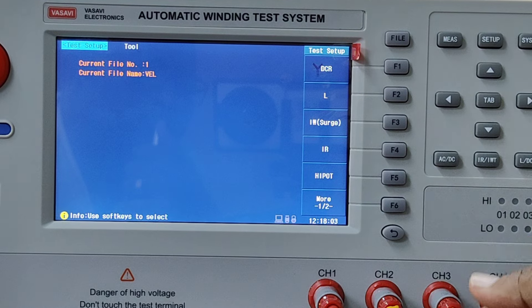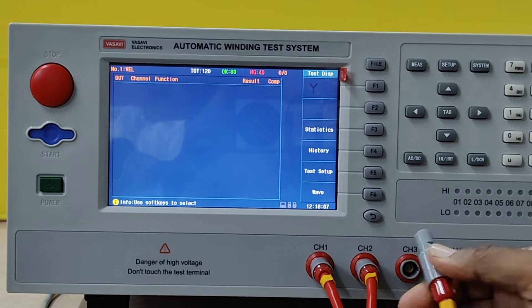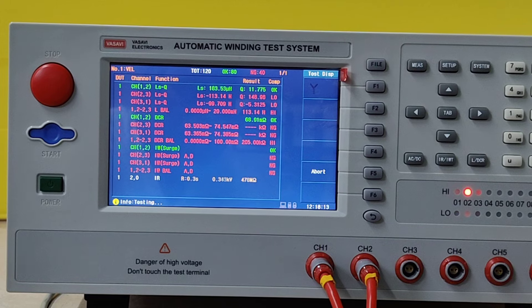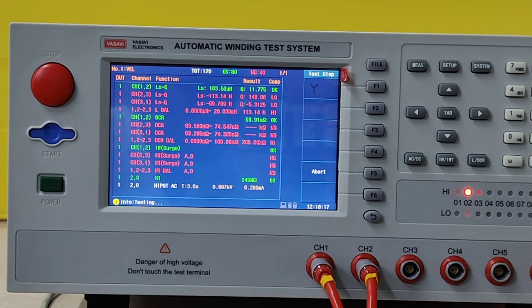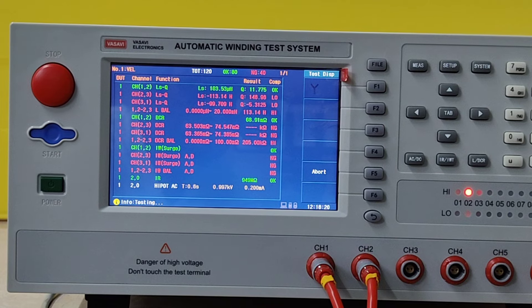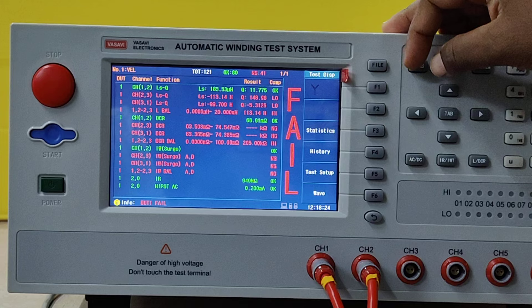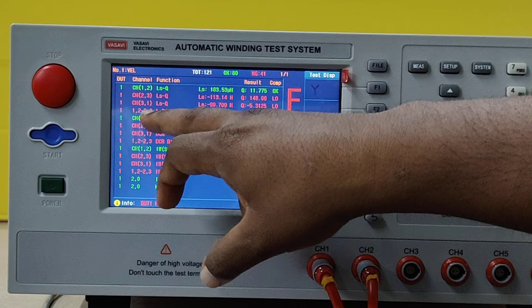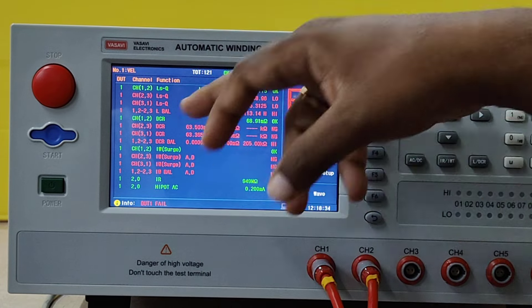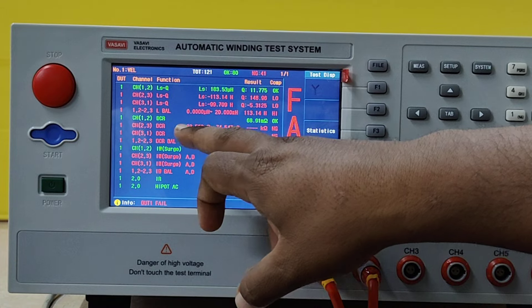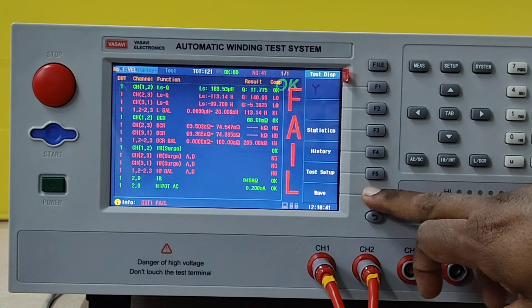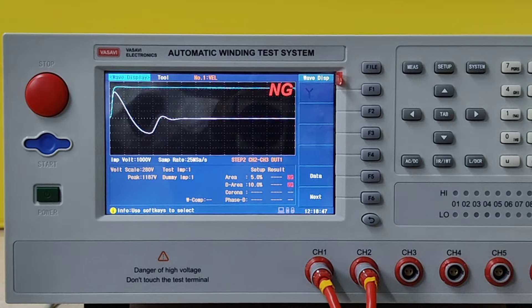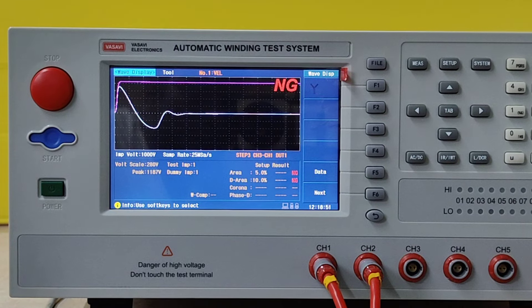Now I will remove one wire — channel 3 — and show you the result. All the parameters linked to channel 3 are failed. Inductance between phases 2-3 and 3-1 is failed. Imbalance is obviously failed because channel 3 is not connected. It is the same way for DC resistance and impulse. You can see the waveform: 1 and 2 is there. For 2 and 3, you can see the waveform. For 3 and 1, the third channel is removed, so the waveform is affected.